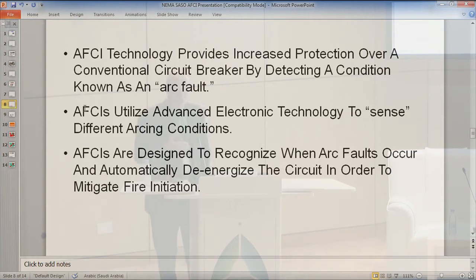And as a result of that, over the years, we've obviously developed it fully, and we've advanced the technology quite a bit. Initially, there were challenges because you're looking at an arcing fault and trying to determine whether or not you have an arcing fault or a ceiling fan or a motor or some other vacuum cleaner kind of device where you've got tons of sparks and everything going on within the armature. You have to determine whether or not that is a problem or if it is an actual out-of-control arcing situation. And so there was more and more development as things went along.